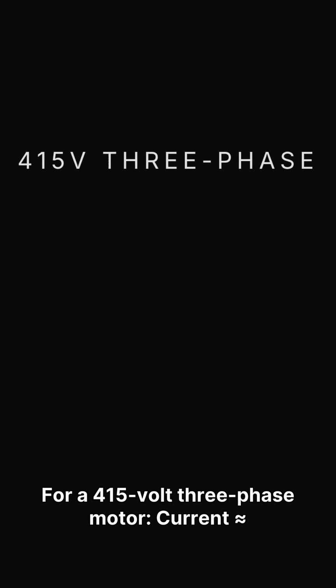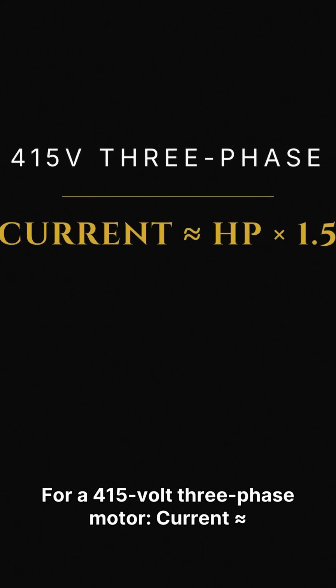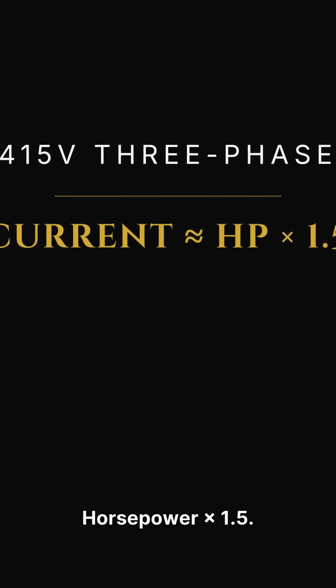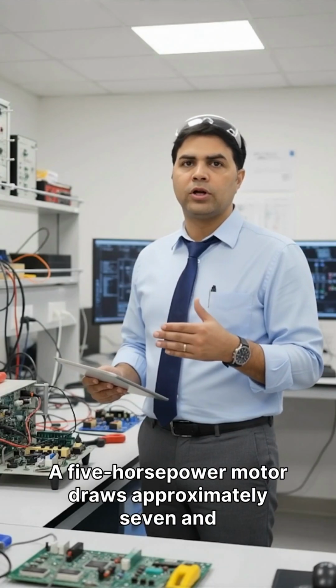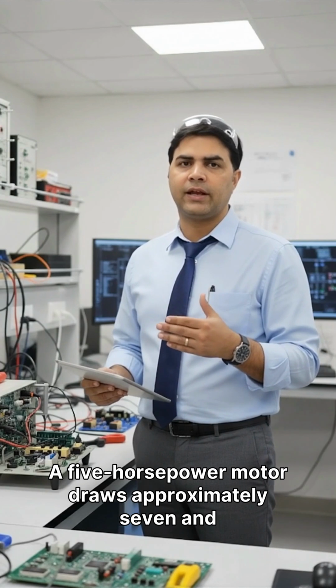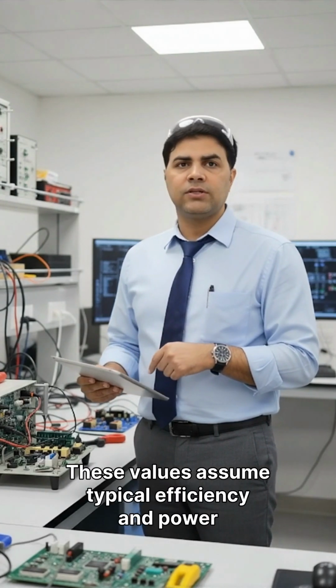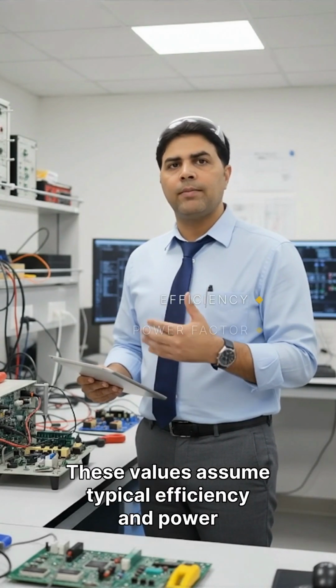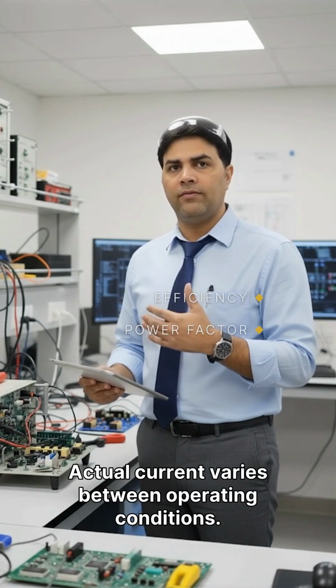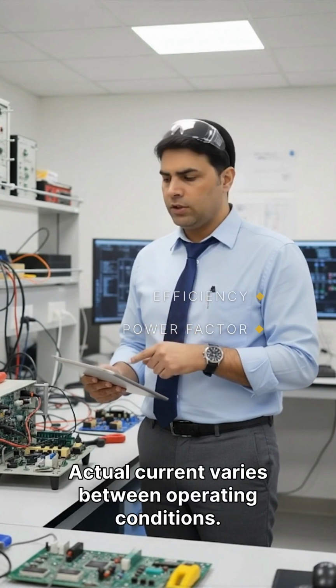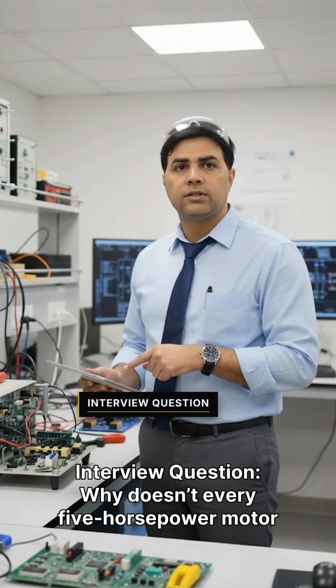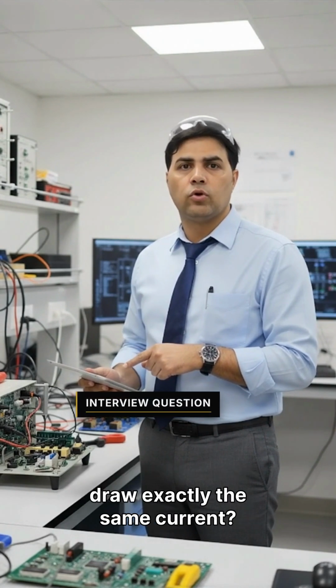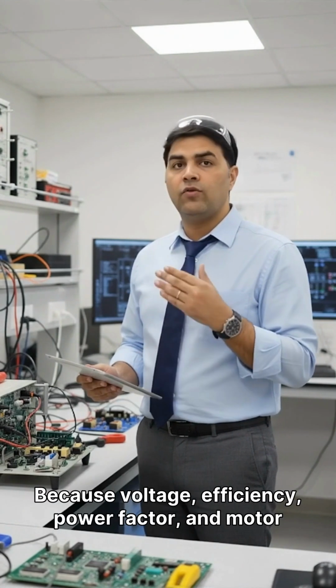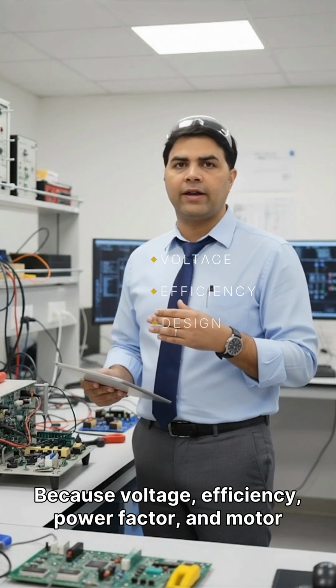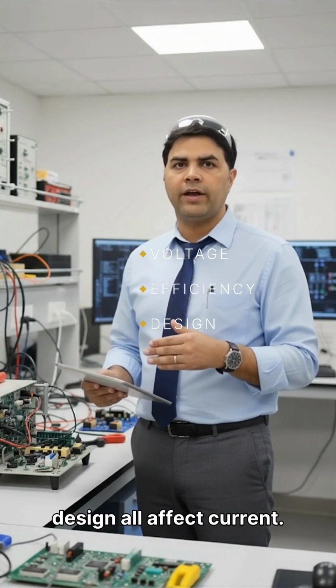For a 415 volt 3-phase motor, current approximately equals horsepower times 1.5. A 5 horsepower motor draws approximately 7.5 amps. These values assume typical efficiency and power factor. Actual current varies between operating conditions. Interview question: why doesn't every 5 horsepower motor draw exactly the same current? Because voltage, efficiency, power factor, and motor design all affect current.